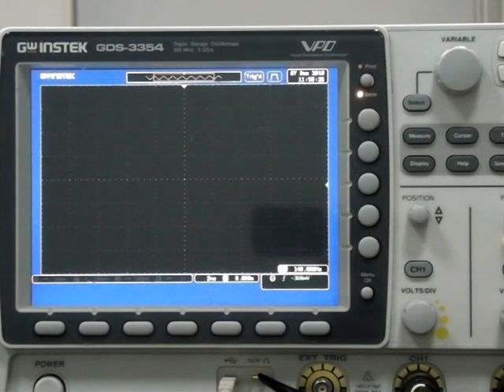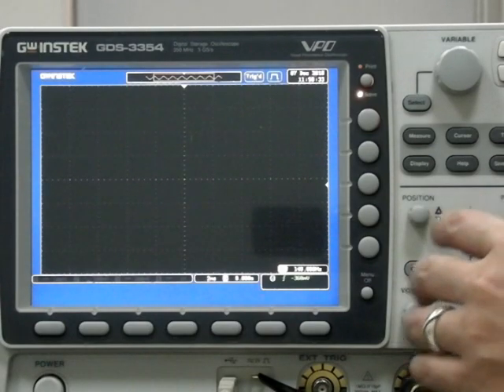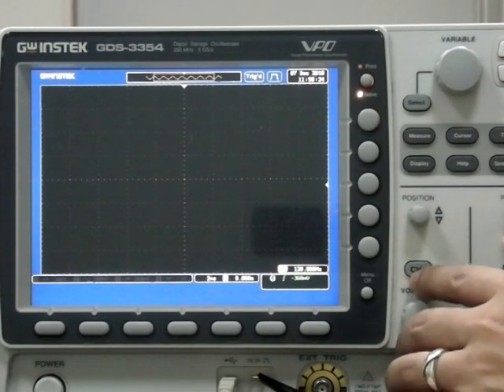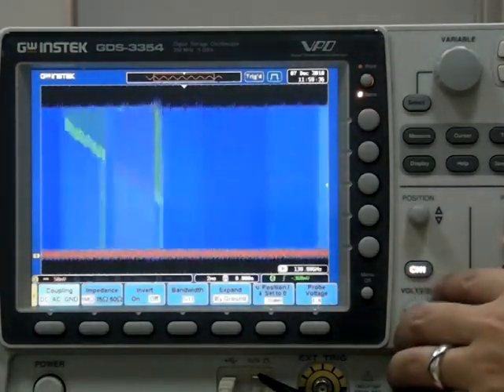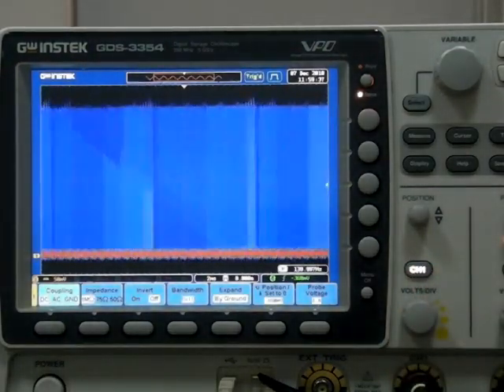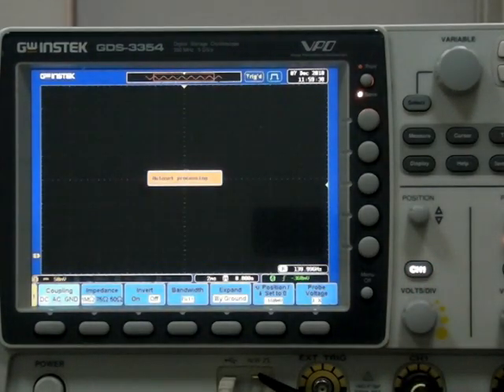First, let's introduce our brand new Waveform Capture Technology, VPO. Start by turning on Channel 1 and input a surge signal. Next, press the Auto Set key and adjust the Time/Div to the best scale.